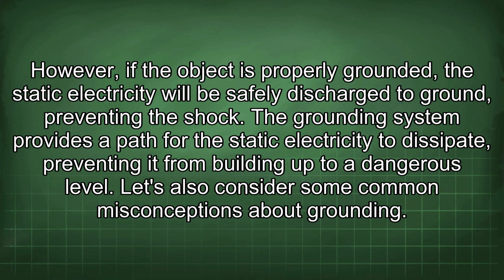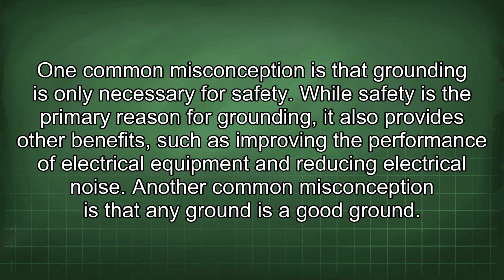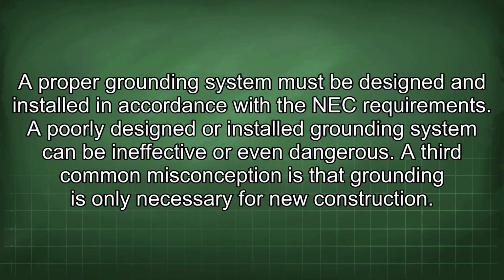Let's also consider some common misconceptions about grounding. One common misconception is that grounding is only necessary for safety. While safety is the primary reason for grounding, it also provides other benefits such as improving the performance of electrical equipment and reducing electrical noise. Another common misconception is that any ground is a good ground. A proper grounding system must be designed and installed in accordance with the NEC requirements. A poorly designed or installed grounding system can be ineffective or even dangerous.